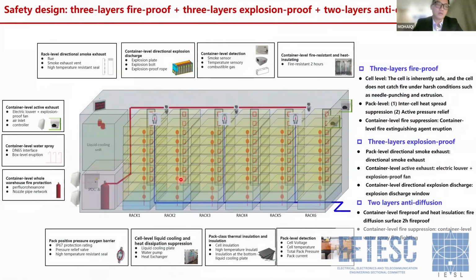As we all know, the battery is a chemical device. If there is thermal runaway, there will be a lot of hydrogen and other types of gas, which is very easy to burn. So when thermal runaway really happens, the battery pack has a one-direction vent to make sure this kind of gas can be relieved in one direction. Because of this vent, if some arc happens inside the cabinet, inside the container, the gas is not there, so it will not cause a fire. So this is for the pack level anti-heat spread.